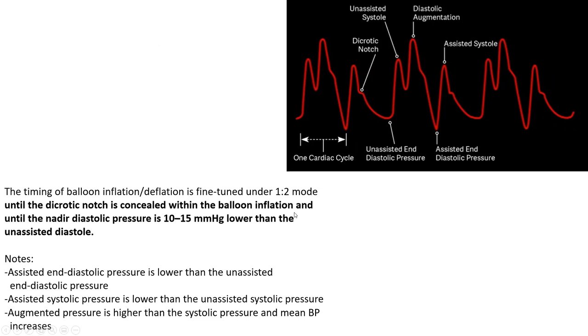And you compare cycles without augmentation versus cycles with augmentation. So here you're getting a systolic pressure, you're getting augmentation, and you're getting what we call the assisted end diastolic pressure and assisted systolic pressure. Those two pressures that follow augmentation, those are what we call the assisted pressures. Conversely, in 1-2 or 1-3 modes, the systolic pressure and diastolic pressure that precede augmentation are the unassisted ones. So you look, this unassisted systole is higher than the assisted systole. This unassisted diastole is higher than the assisted diastole. And that's what you should see.